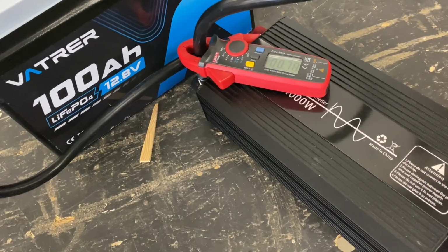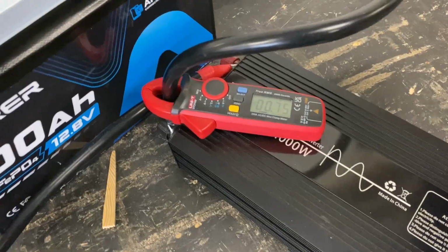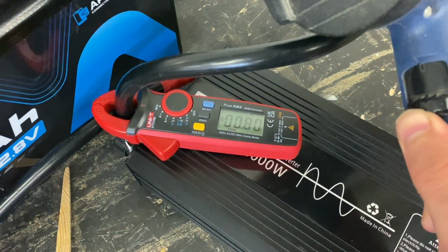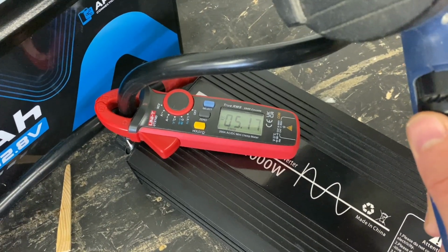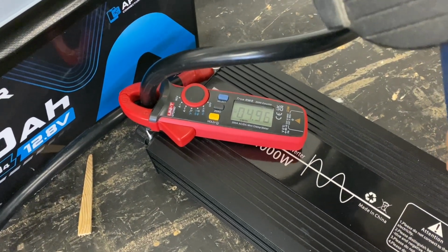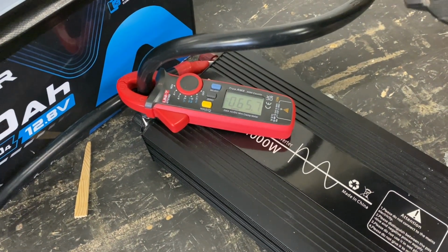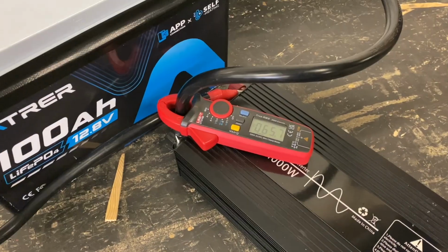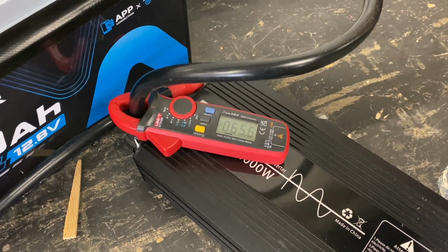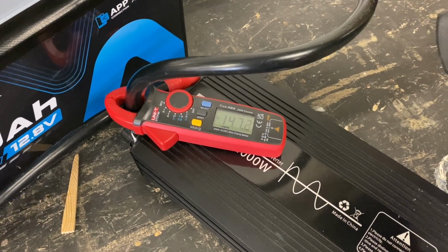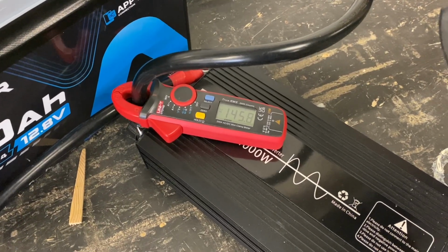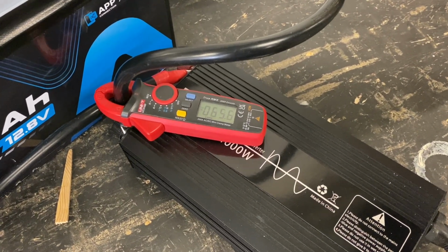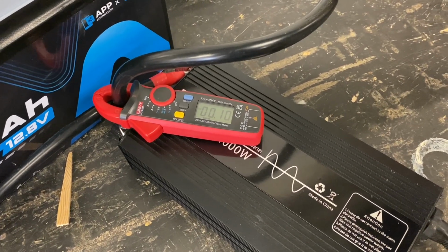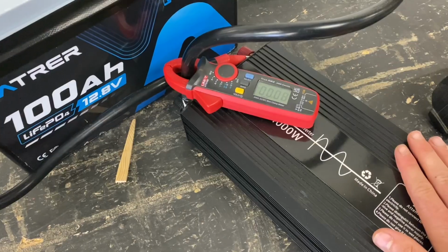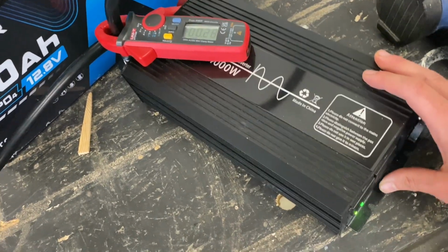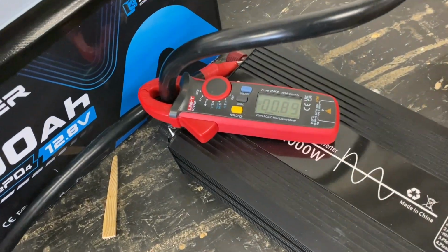DC amp reading, plugging in the heat gun. Now let's just put it in fan mode. Five amps... 65 amps. Now the next level should trip the overcurrent protection in the BMS. Let's see. Yeah, there we go. 145 amps—let's see if it resets. It does. Let's do it again.